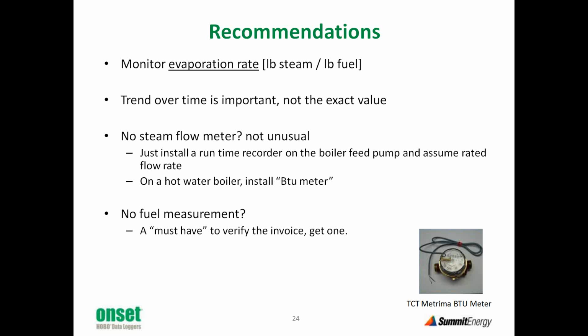Fortunately, my friends at Onset have a little gadget. What you can do is just put a runtime recorder on the boiler feed pump, and you can assume a flow rate. If you just know the runtime on the boiler feed pump, that'll give you a pretty good idea of the pounds of feed water that eventually convert to pounds of steam. Surely you have a meter on the fuel. You're buying it probably, and so you typically have a measurement on the fuel. A simple runtime on the boiler feed pump could get you the data that you need to monitor that evaporation rate.